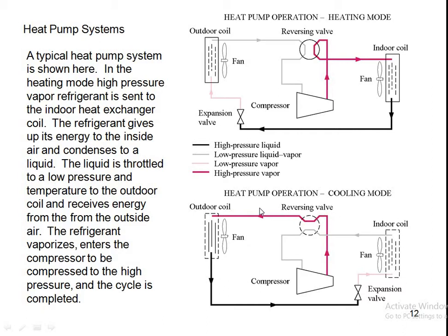If we reverse this direction, that will be the cooling mode. In cooling mode, the compressed vapor goes through the reversing valve to the outdoor coil, rejects its heat there, converts into liquid, then comes to the expansion valve where the pressure is reduced. It then receives heat from the indoor coil, converts into vapor, and goes to the compressor. This is the basic difference between the heating and cooling mode of heat pump operation.